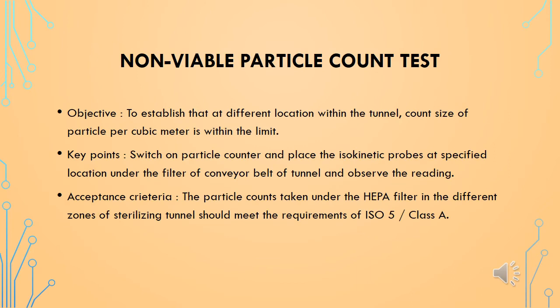A three percent variation is considered acceptable to the set speed. The fourth qualification test is non-viable particle count. The objective of this test is to establish that at different locations within the tunnel, the count and size of particles per cubic meter is within the limit. To perform this test, particle counters are used, wherein isokinetic probes are located at a specified location under the filter of the conveyor belt of the tunnel, and readings are observed.